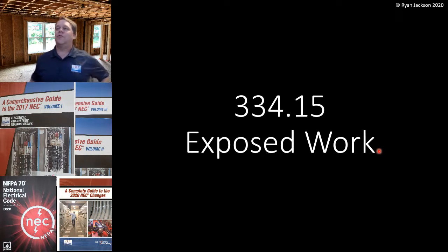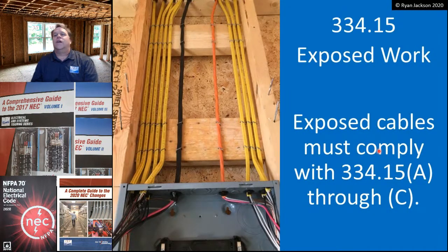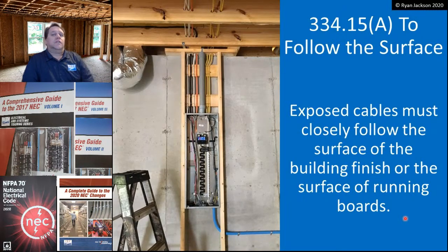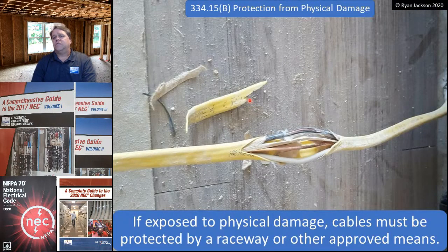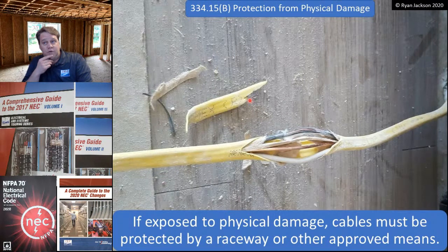Exposed work, 334.15. Yes, you can run NM cable exposed. Of course you can. We got a whole section titled Exposed Work. How many times have you guys heard that you can't run NM cable exposed? Of course you can. Exposed cables must comply with 334.15(A) through (C). They have to closely follow the surface of the building or the surface of running boards. All right, beautiful installation right there. So we've got following the surface of the running boards. I think that complies. If it's exposed to physical damage, then cables must be protected by a raceway or other approved means. Okay.